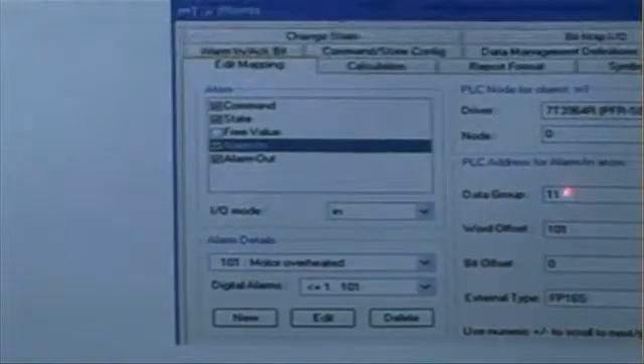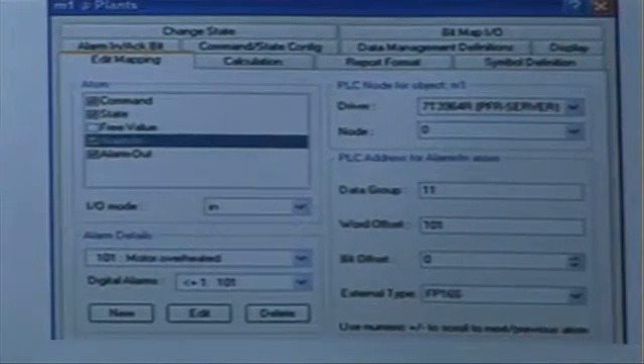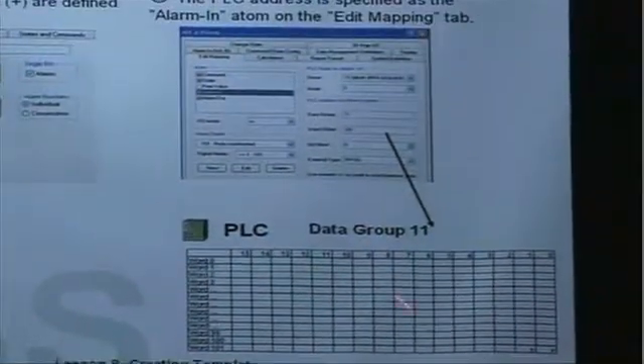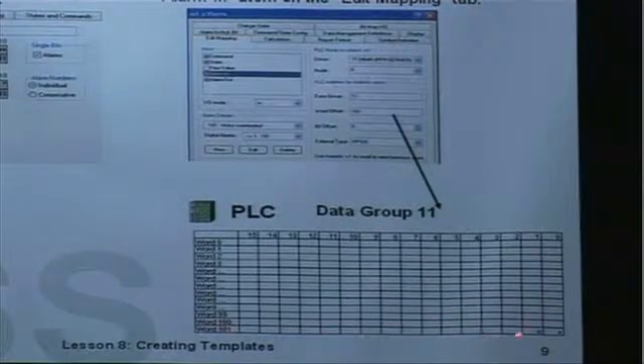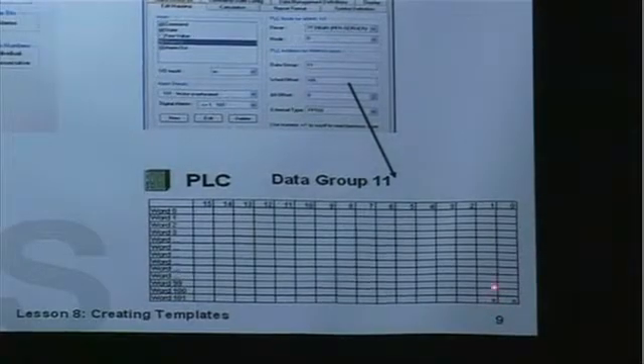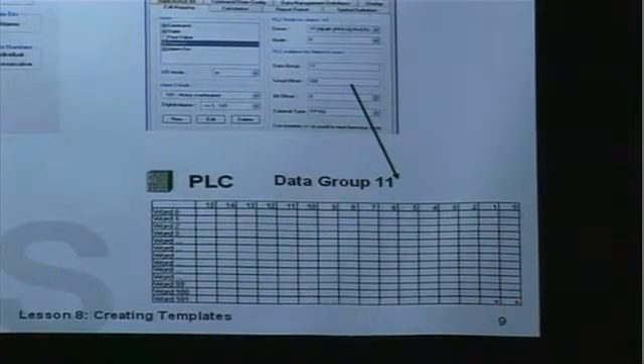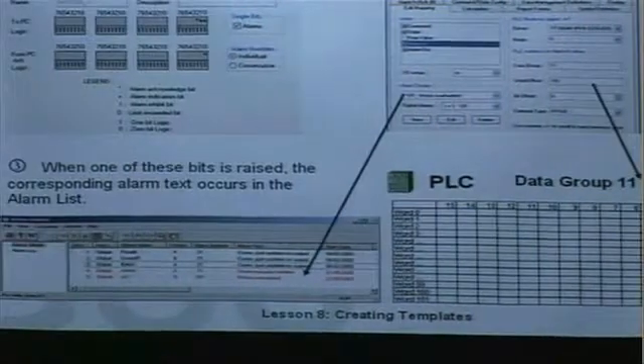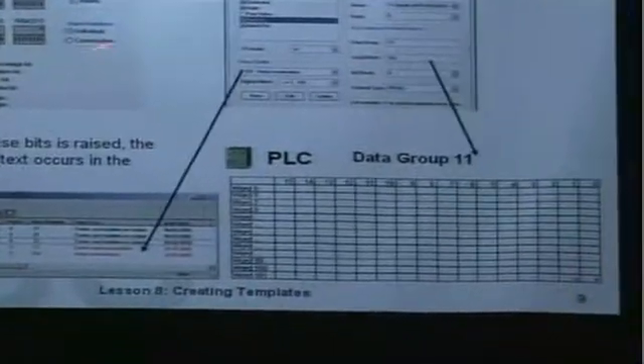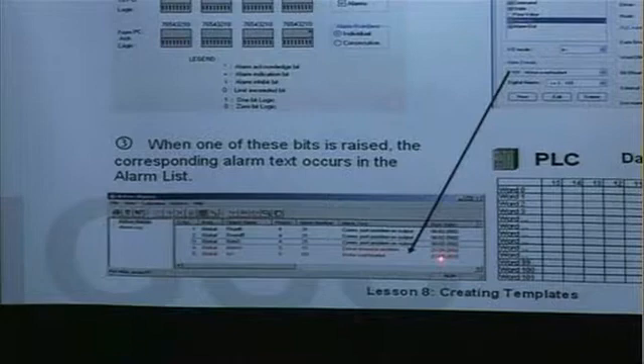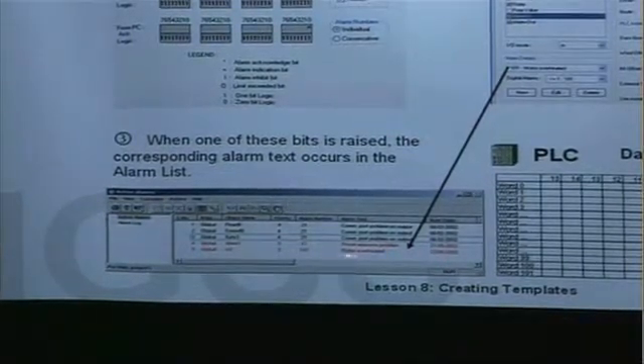We have specified data group 11, word number 101. To illustrate this, we look into the PLC and we are looking into data group number 11, on word number 101, bits 0 and 1 — those are the alarm bits we have set. So if one of these bits is raised, it means that the alarm will occur in IGSS. The PLC will send that bit to IGSS and we will see the alarm in the alarm list.